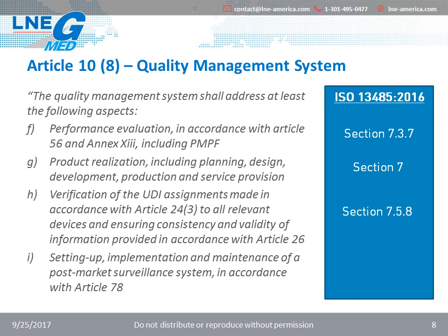The regulation also calls to cover aspects related to post-market in the QMS. This section is correlated to sections 8.2.1 and 8.5.1 of the ISO 13485:2016 version. So 8.2.1 is related to feedback. It clearly mentions in that section that if applicable regulatory requirements require the organization to gain specific experience from post-production activity, the review of this experience should form part of the feedback process. The other section, 8.5.1, relates to improvement of the QMS, for which the results of the post-market should be taken into account to maintain the effectiveness of the quality management system.